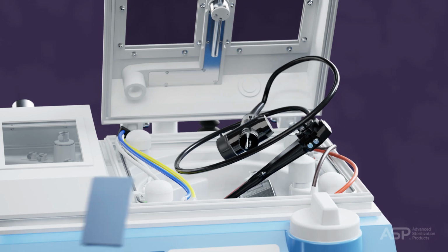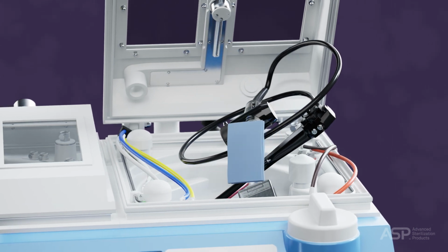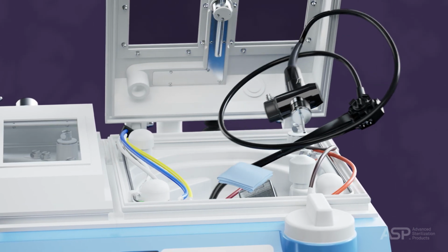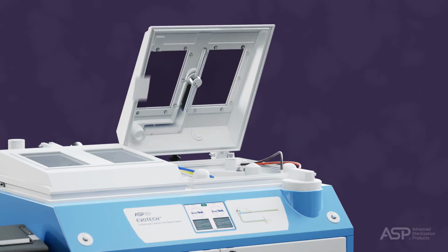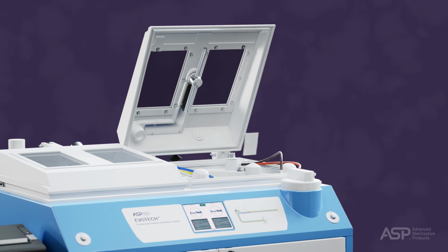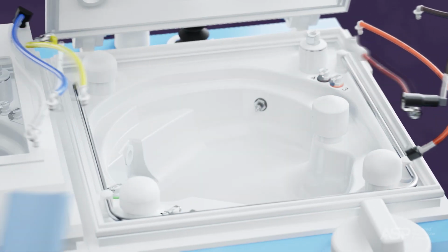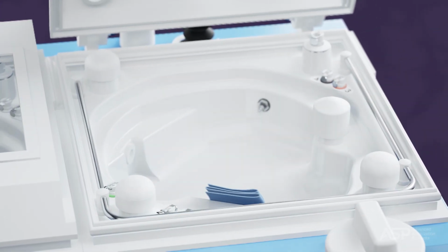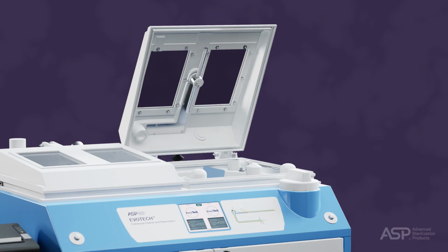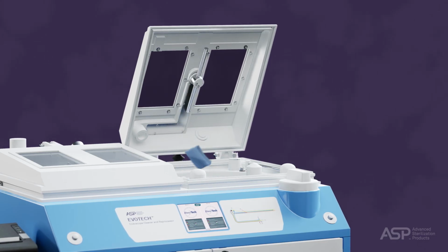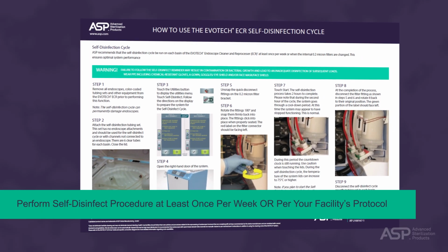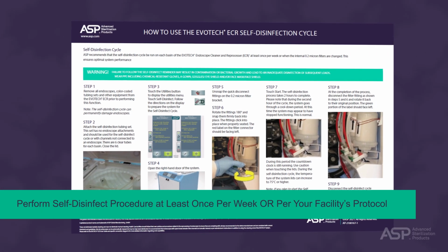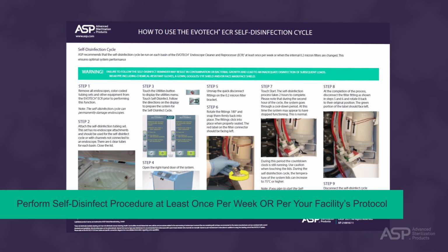After the last cycle of the day, remove endoscopes from the basins using established infection control practices to prevent recontamination of the endoscope. Wipe the edge seals with alcohol, remove and store all connectors, wipe the basin with a clean, lint-free cloth, then leave the system switched on to reduce startup time for the next day. ASP recommends the self-disinfect procedure be performed at least once per week or per your facility's protocol.